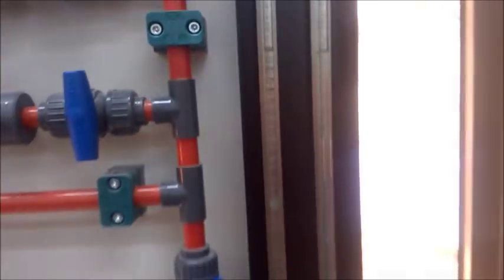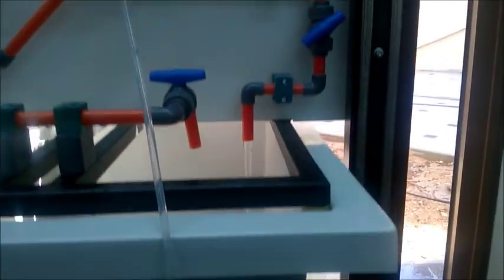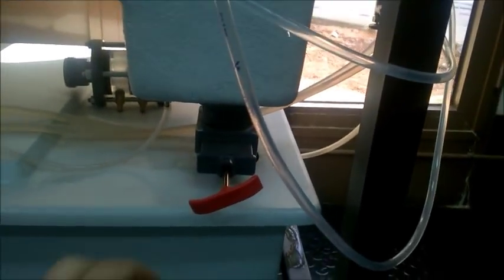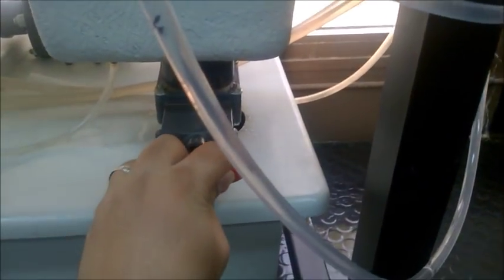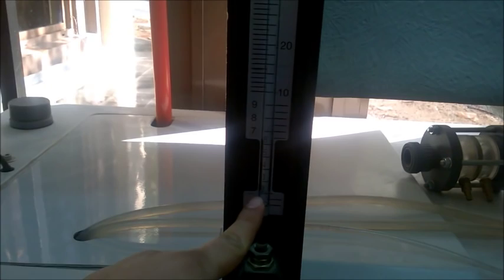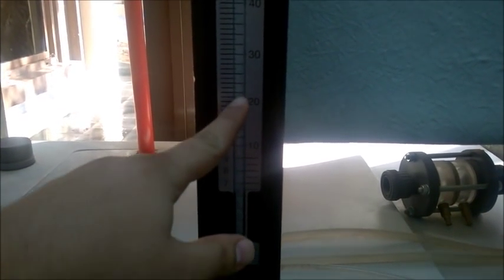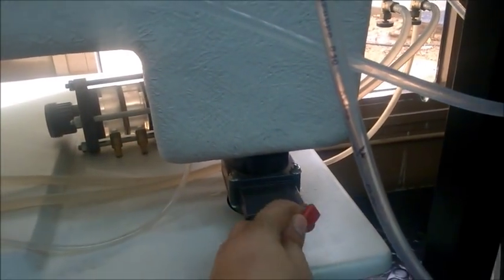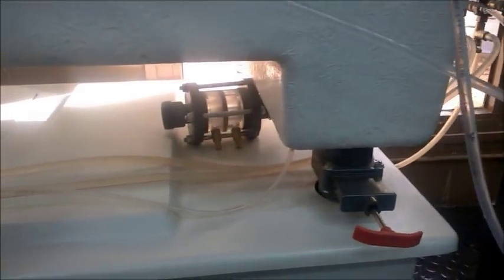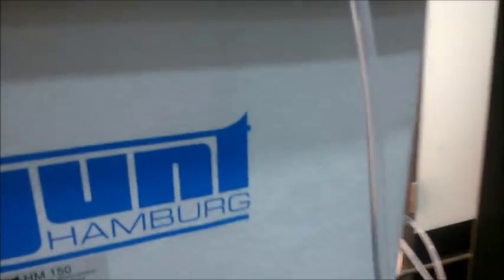In order to determine the volumetric flow rate, we should carry out a time-volume collection. So close the volumetric valve and by using your stopwatch, determine how many liters accumulated in the tank. Then open the volumetric valve again to allow accumulated water to drain off the system.